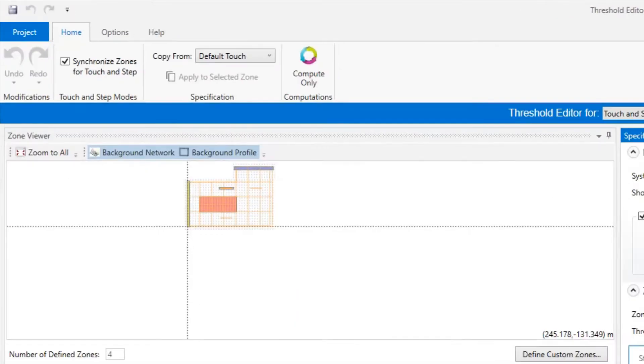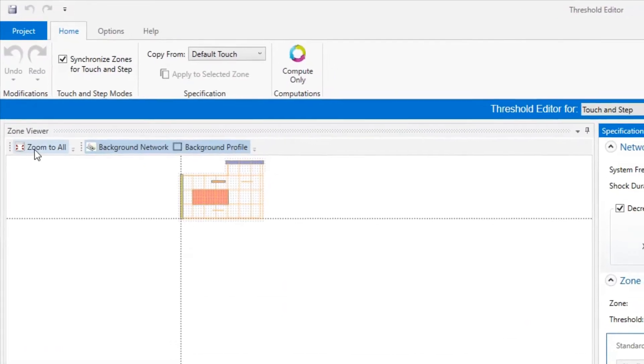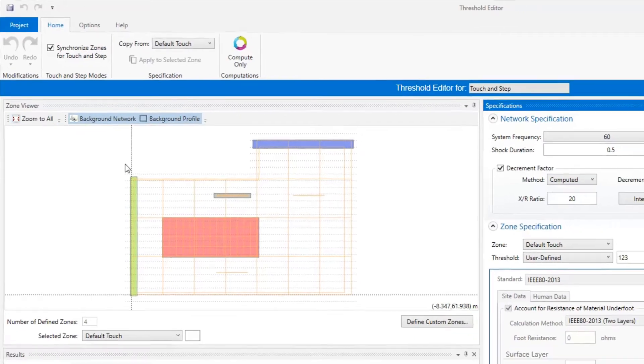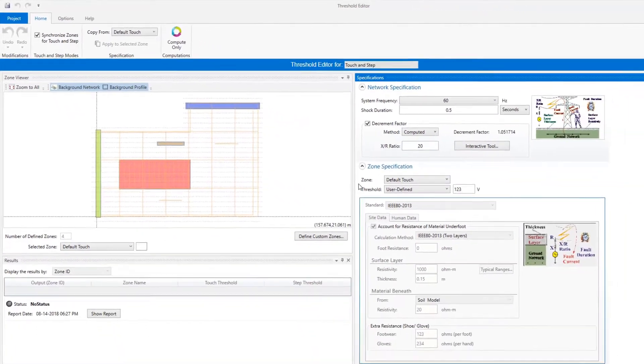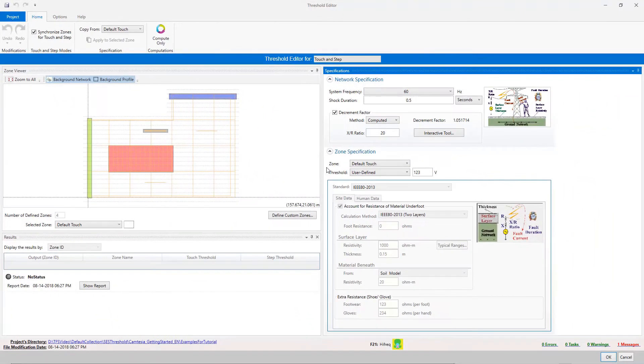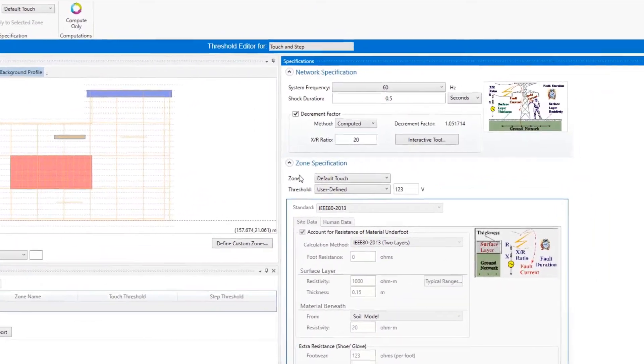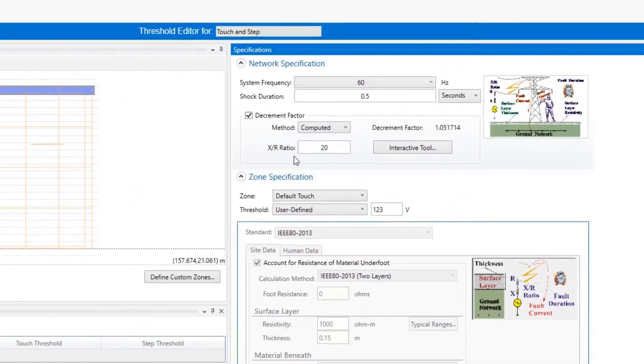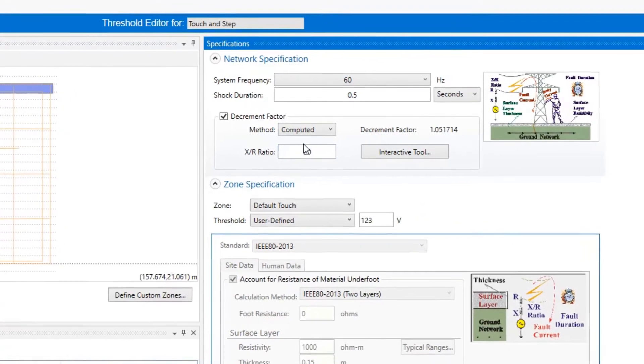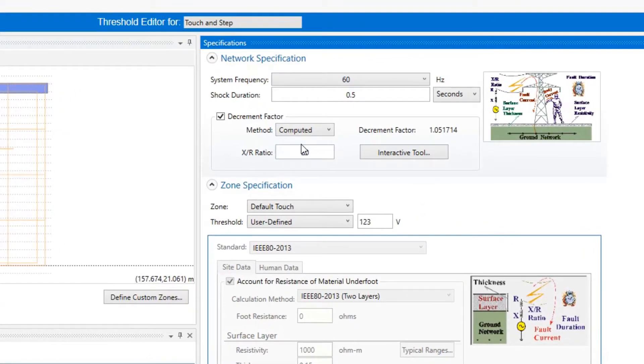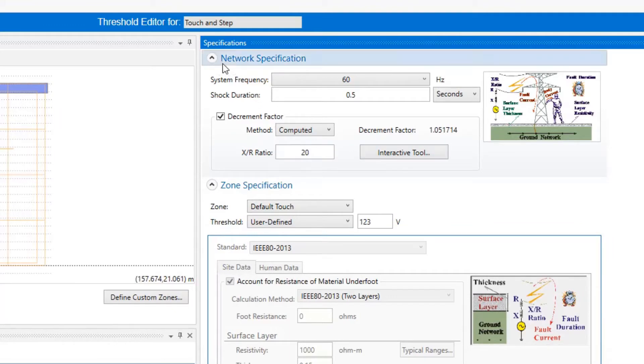The SCS Threshold interface is organized in four panels. First, the Network Specifications panel at the top right defines the system-related characteristics like frequency, shock duration, and decrement factor, and these values will be the same for all defined zones.